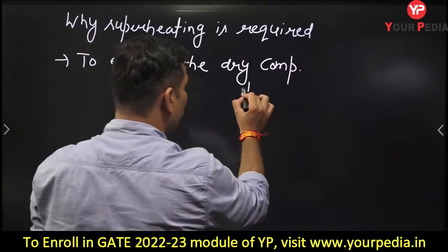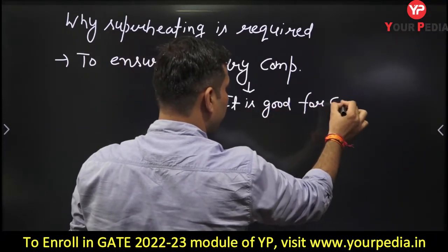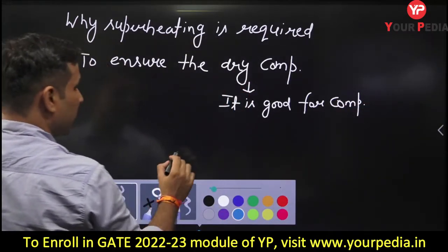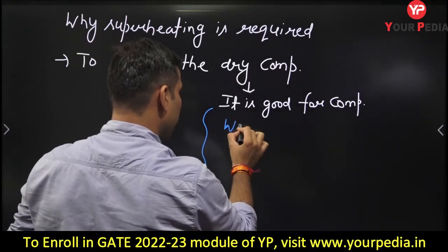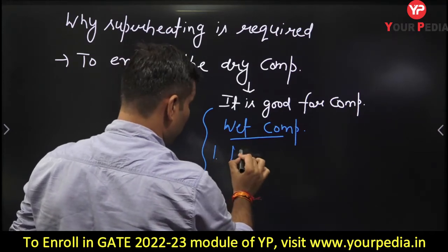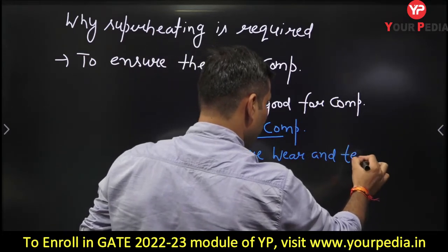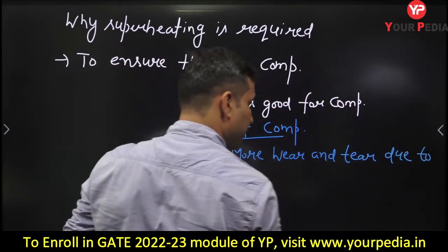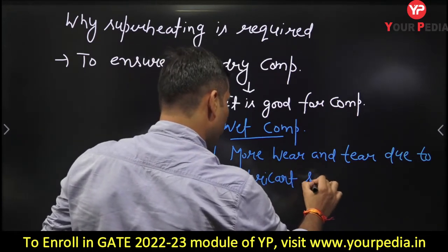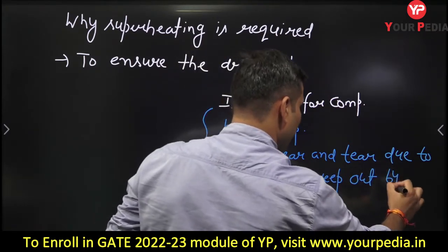Why? Because this is good for the compressor. Whenever there is wet compression, there is more wear and tear, due to the lubricant being swept out by the refrigerant.